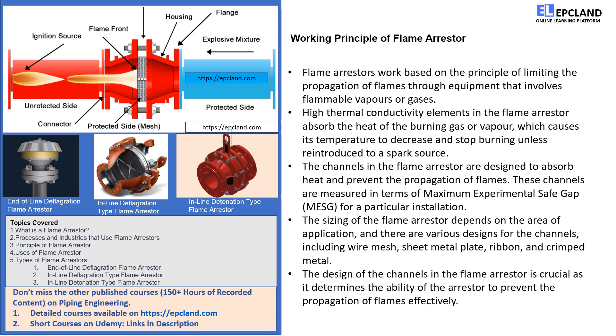Welcome to the second topic in our video lecture series on flame arrestors. In this section, we'll explore the principle behind how a flame arrester works. A flame arrester operates on the principle of absorbing the heat of burning gases or vapors, which reduces their temperature and prevents them from igniting again. This is achieved through the use of high thermal conductivity elements that are designed to absorb the heat and prevent the flame from propagating. The channels within a flame arrester are designed to absorb heat, and the size of the channels is measured in terms of maximum experimental safe gap (MESG) for a particular installation. The MESG is the largest gap through which a flame cannot propagate under test conditions.